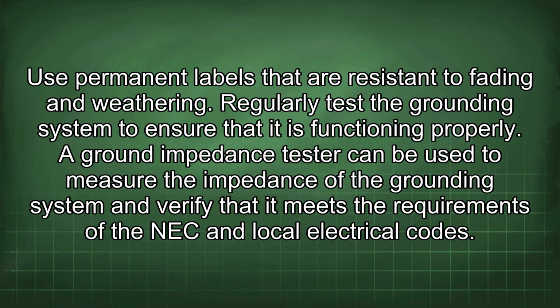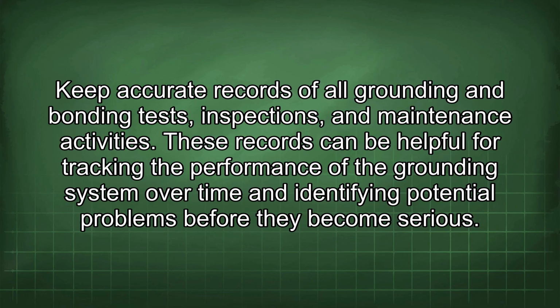Regularly test the grounding system to ensure that it is functioning properly. The ground impedance tester can be used to measure the impedance of the grounding system and verify that it meets the requirements of the NEC and local electrical codes. Keep accurate records of all grounding and bonding tests, inspections, and maintenance activities. These records can be helpful for tracking the performance of the grounding system over time and identifying potential problems before they become serious.